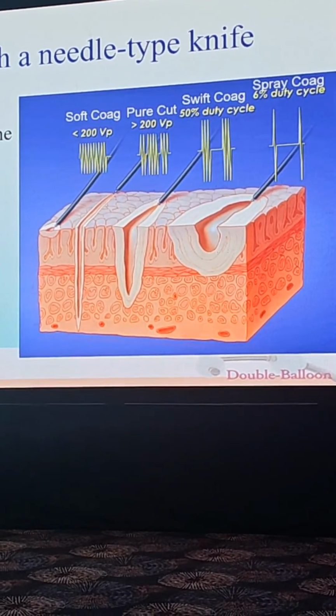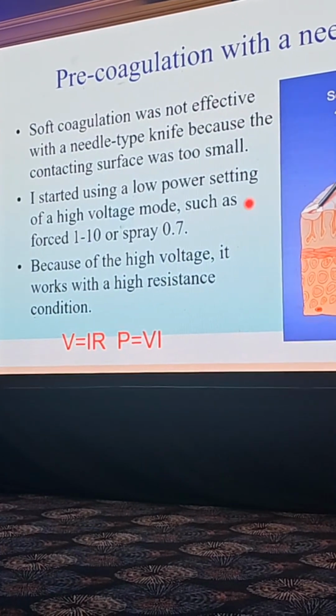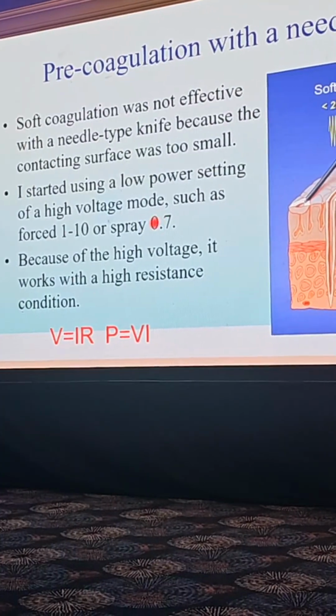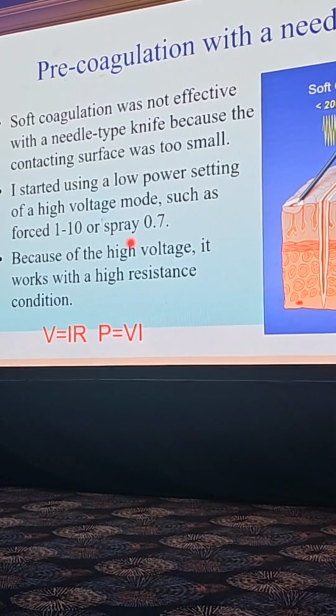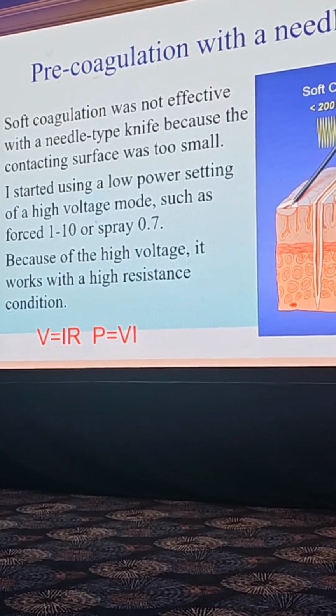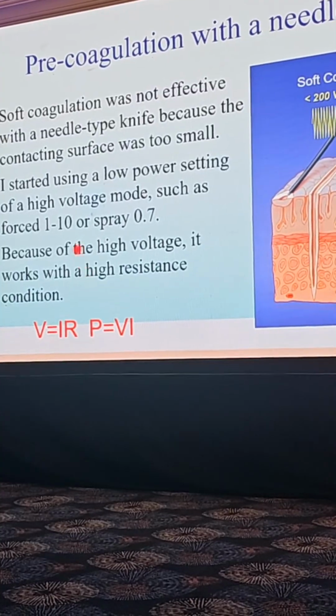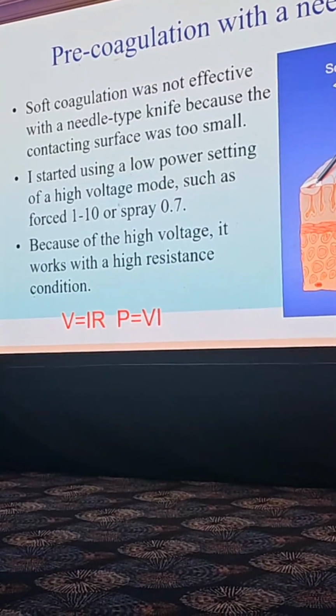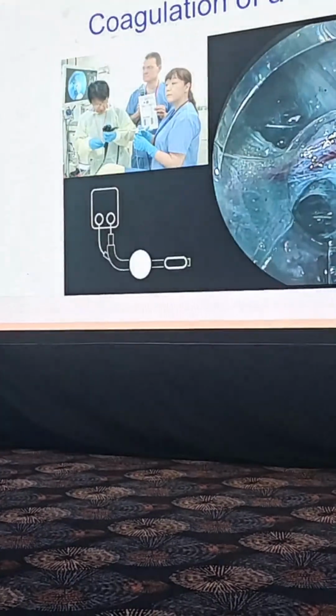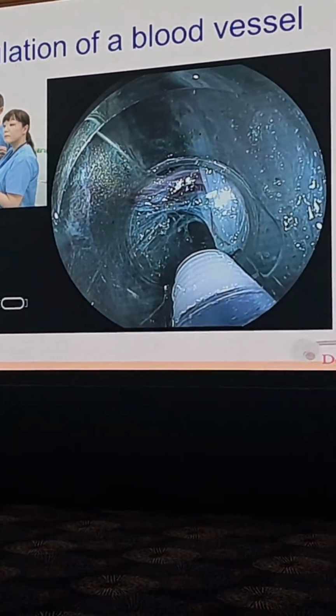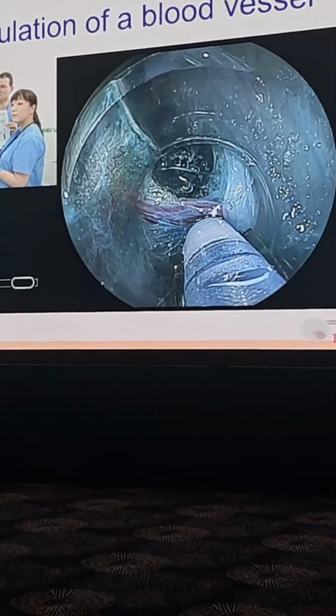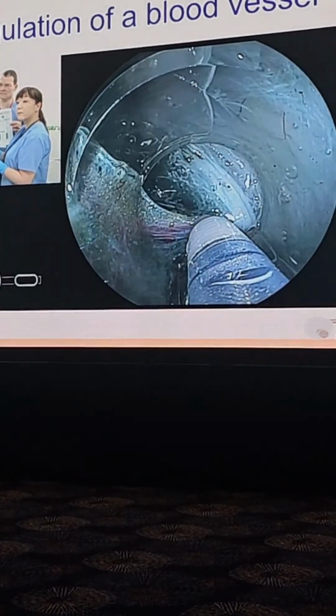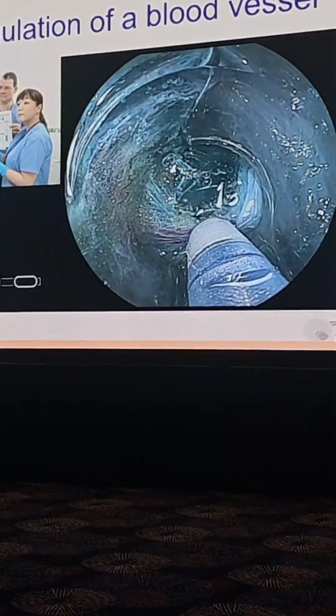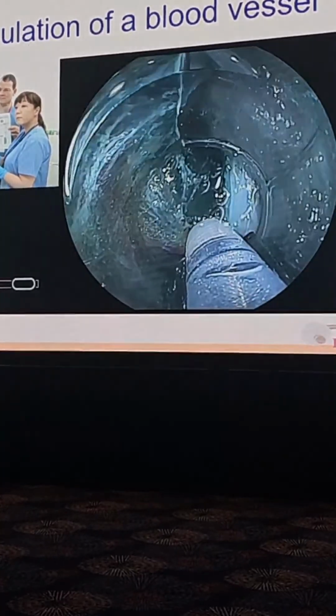Then what I did was, instead of using a low voltage mode, I tried low power setting, such as spray coagulation 0.7. In this setting, I tried to limit the power by limiting the current. Voltage is high, but current is low. So even with high resistance, it works. So this is the one: the very weak spray coagulation, 0.7 by VIO 3, 0.7 spray coag works for precoagulation in CO2.